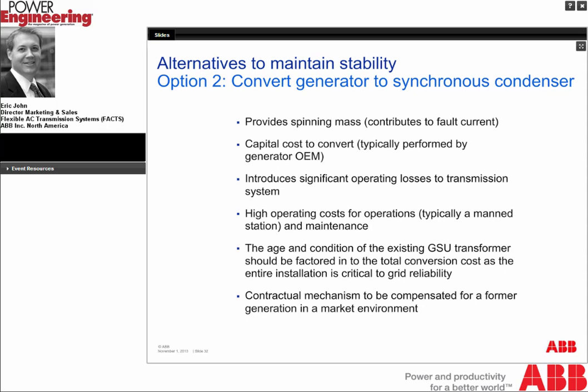The operating losses that would then be part of the transmission system for a synchronous condenser can be quite substantial. And of course, many utilities these days have initiatives to reduce their overall system losses. Similarly, you have ongoing costs in the form of operations. A generator that's been converted, especially if it has a hydrogen cooling system or a big lube oil system, is often a manned station. And so you have ongoing costs for the O&M folks who would operate the station.